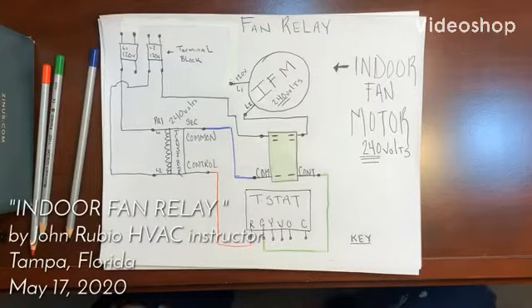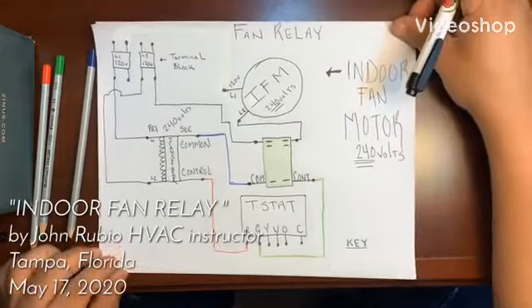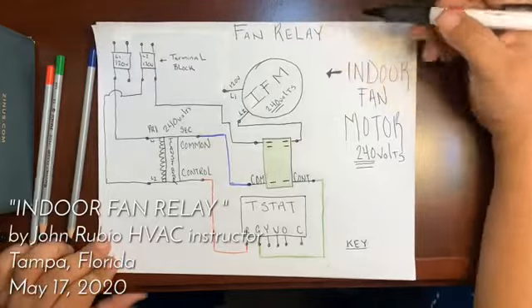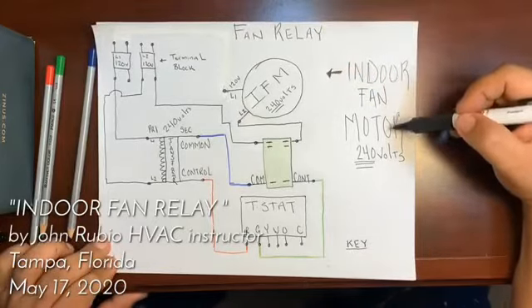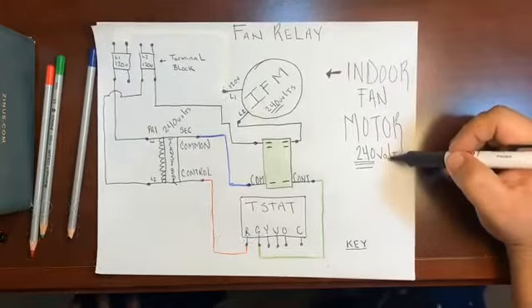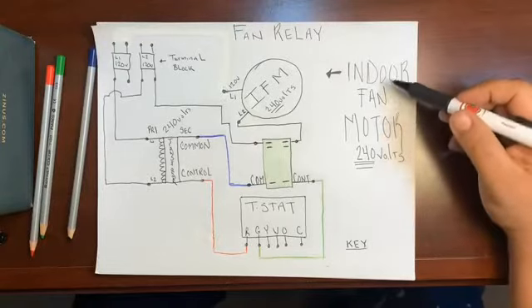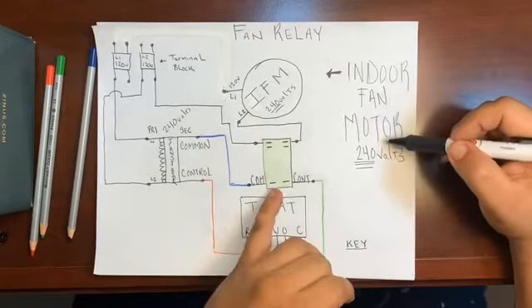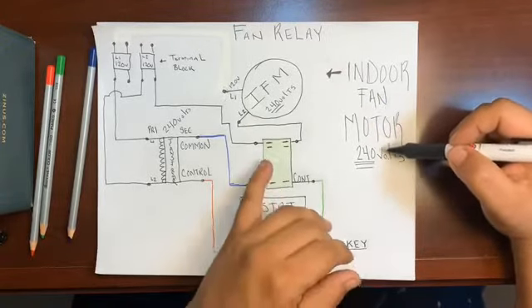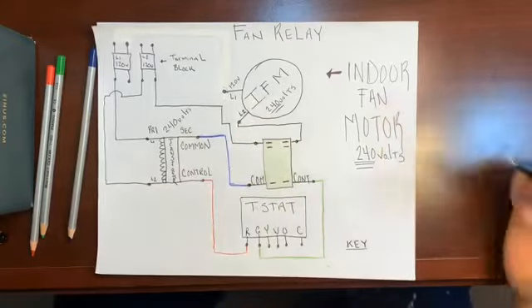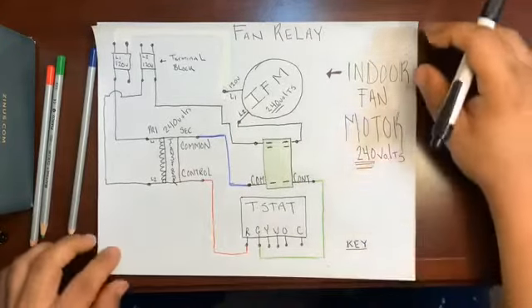HVAC department, we're talking about the fan relay. We're talking about how the fan relay is going to activate the indoor fan motor with the 240 volts that the indoor fan motor needs. The fan relay is going to provide half of that voltage to turn on the fan motor when it's time. So let's quickly go over our diagram together.